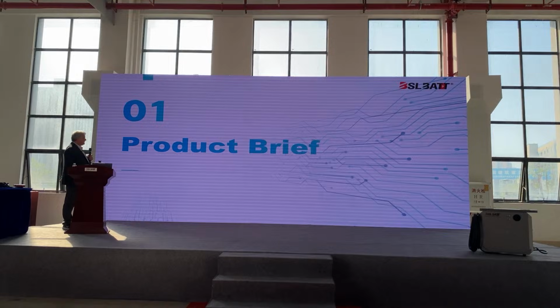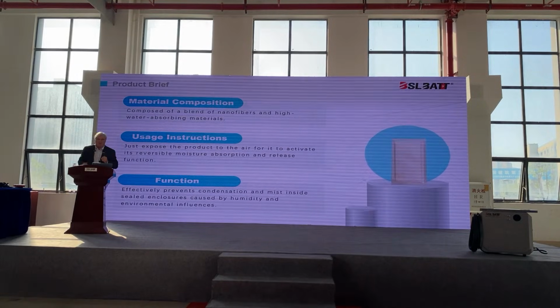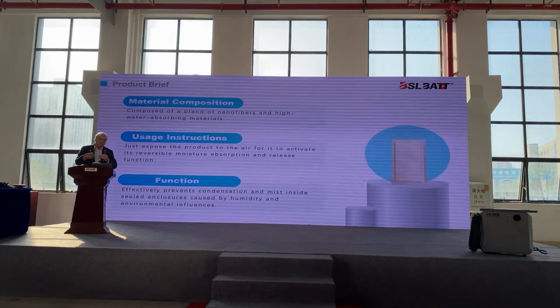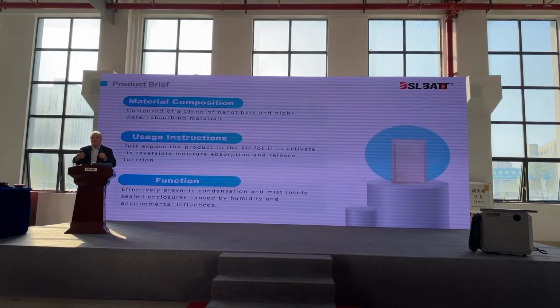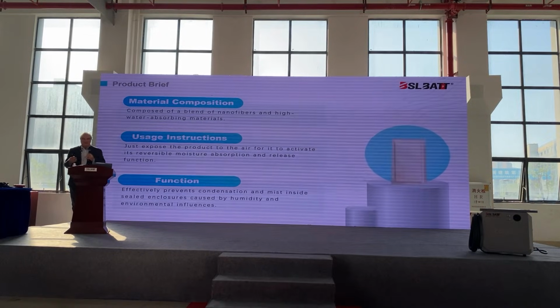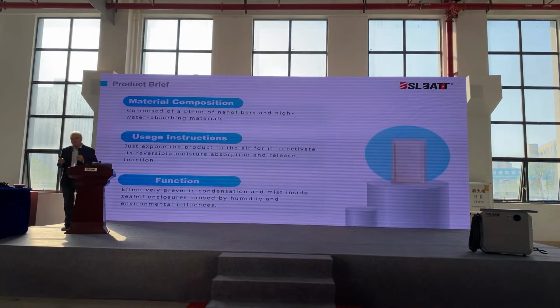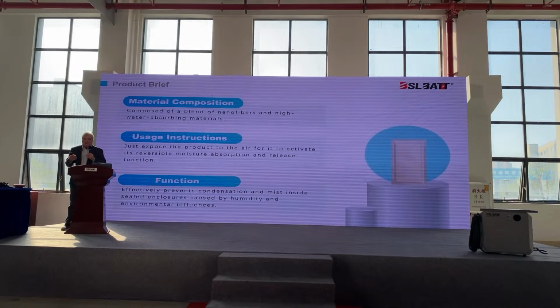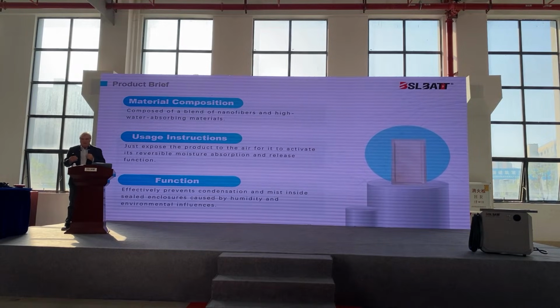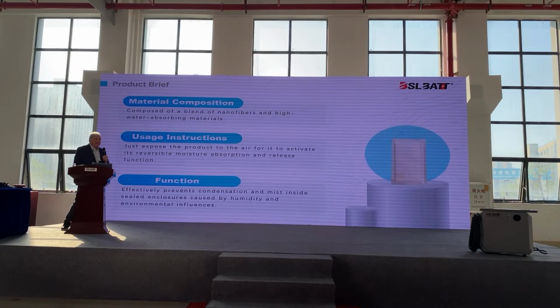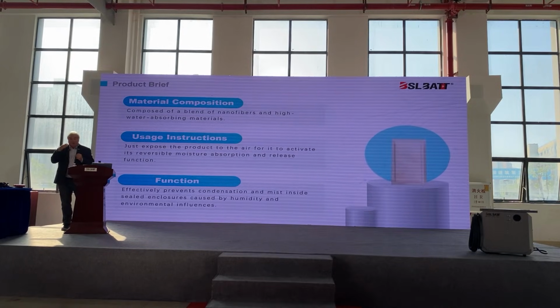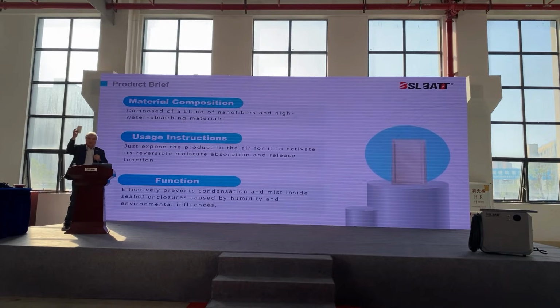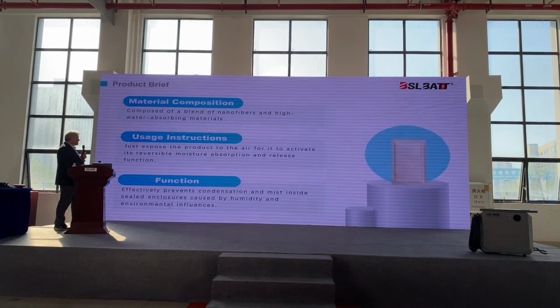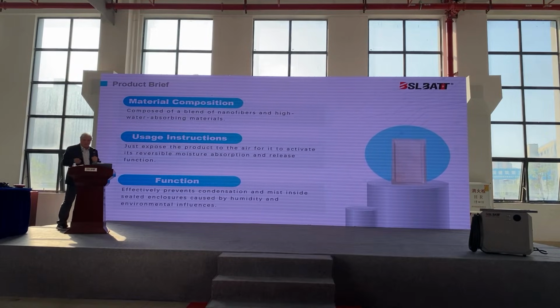What this does is allow us to take humidity, moisture, in a contained battery box. We'll have a battery box that could be IP54, IP65 sealed, a sealed environment. But if we have a high humidity application and there are ambient temperature differences where the air is saturated and the metal container becomes cooler, we're going to get some moisture. Even though the battery case itself is sealed, there's going to be moisture present inside that battery, and that can cause damage, it can cause corrosion, it could be minor, it could be fatal, but there's still moisture present. So with this material we're working with now, we can apply this inside the battery, and it's a reusable type of material, composed of nanofibers, a high water absorbing material.